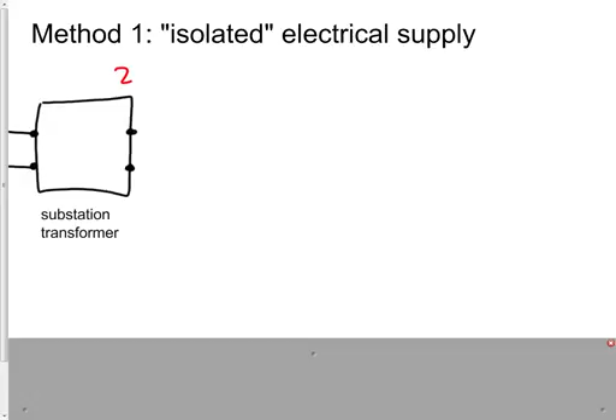Now, method one of power distribution would be to make what's called an isolated electrical supply, which has some benefits to it and some drawbacks. So what we have is a wire coming from one terminal here and a wire coming from the other terminal there. These are insulated wires, and nothing in this system is connected to the ground, to the earth itself.